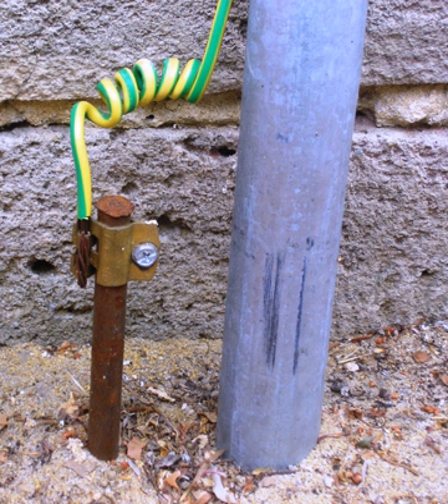In a polyphase AC system, an artificial neutral grounding system may be used. Although no phase conductor is directly connected to ground, a specially constructed transformer, a zigzag transformer, blocks the power frequency current from flowing to earth, but allows any leakage or transient current to flow to ground.